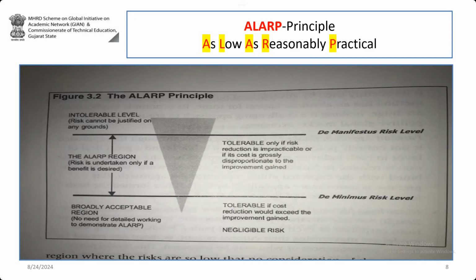Now, this is a slide which is taken from the book, which I showed you the picture of. This is known as the ALARP principle, as low as reasonably practical. Based on this slide, people are going to design the SIL level. Above this level is not tolerable. Risk cannot be justified on any grounds. That means if you are in this region, you cannot run the plant. It is not acceptable to management or to the people, and you have to reduce the risk.